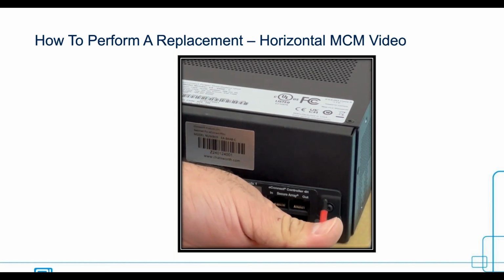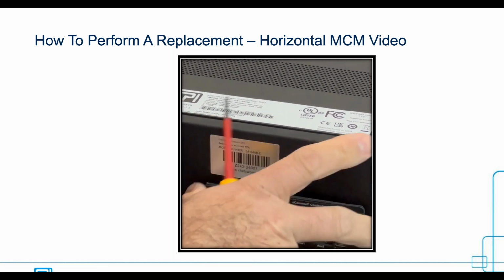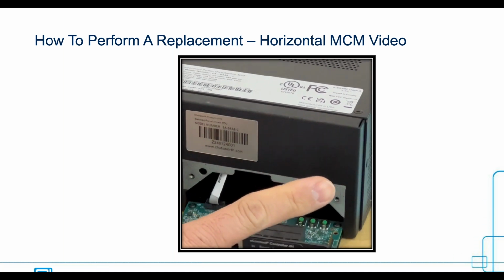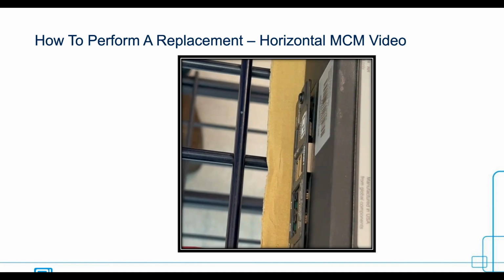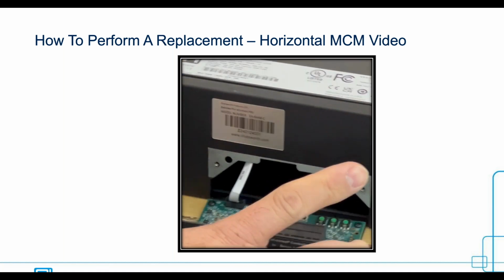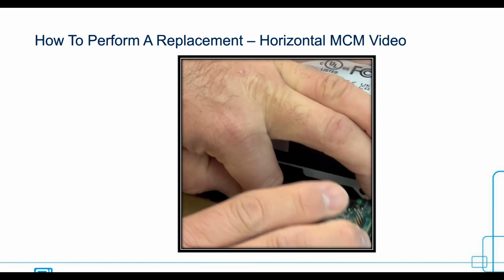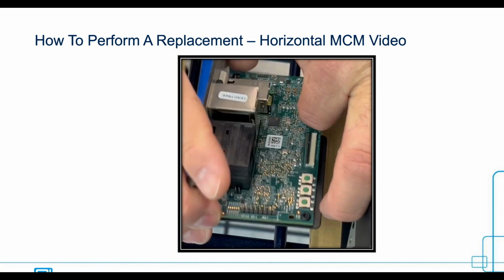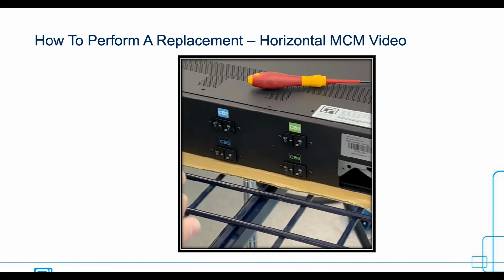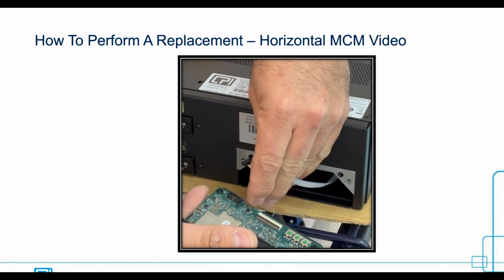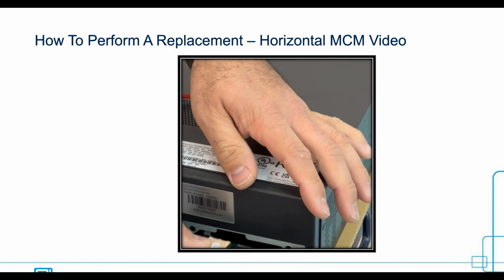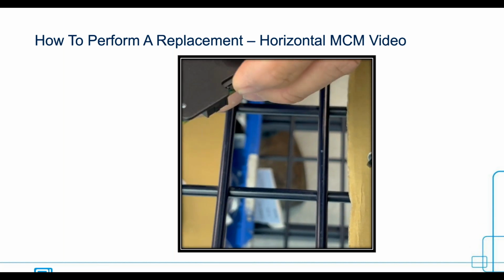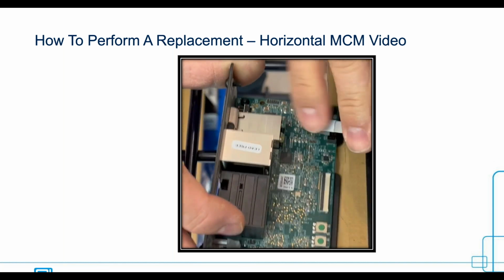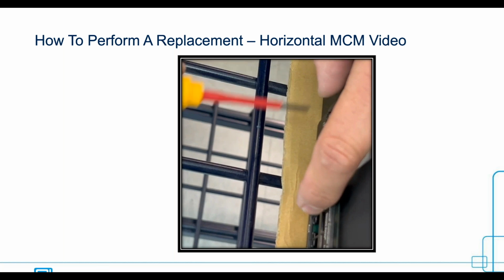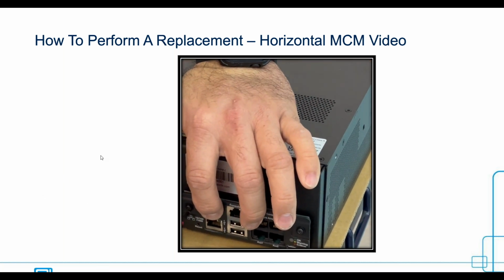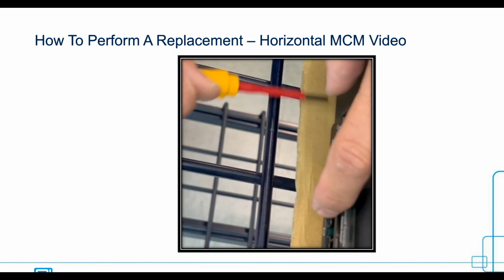So in this one, we have two screws. We're using the T10 driver. And this one is going to come out a lot easier compared to a vertical controller module. Here we disconnect the CAN bus connector. Insert the SD card. And there you go. That is the horizontal controller module. And this one is going to be the eConnect Controller 4.